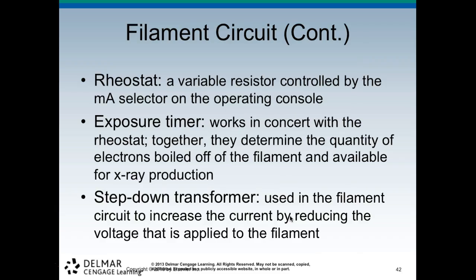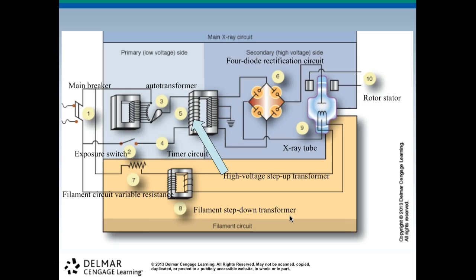Okay, so on the filament circuit side, we have the rheostat, and what is that? It's a variable resistor controlled by the mA selector on the operating console. There's an exposure timer, so it works in concert with the rheostat. Together, they determine the quantity of electrons boiled off the filament and available for X-ray production. There's a step-down transformer. It's used in the filament circuit to increase the current by reducing the voltage that is applied to the filament. So here is the whole thing all together.